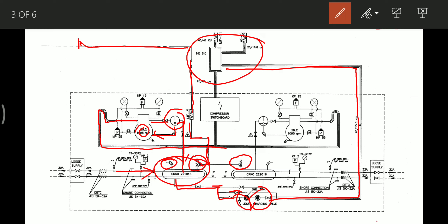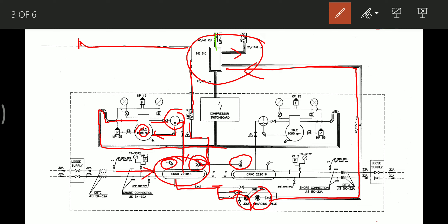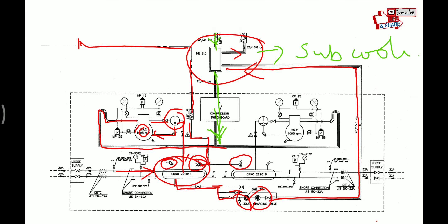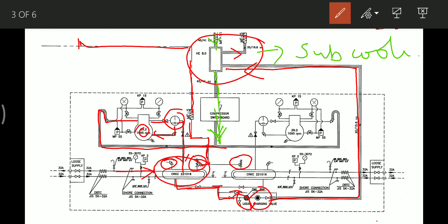After the filter and dryer, the refrigerant passes through a sight glass and then to the evaporator. Before the evaporator, it passes through a heat exchanger. The liquid coming from the condenser and the vapor coming from the evaporator pass through this heat exchanger, which actually acts as a sub-cooler.